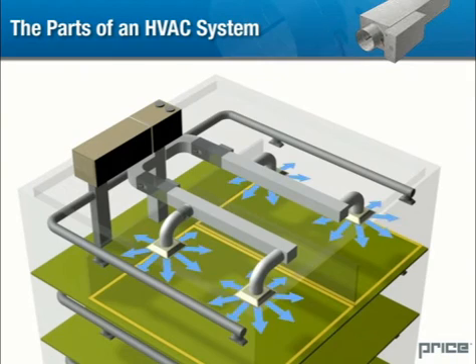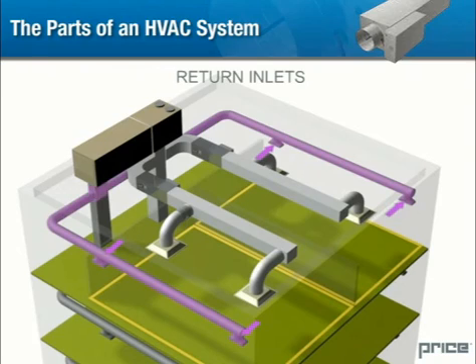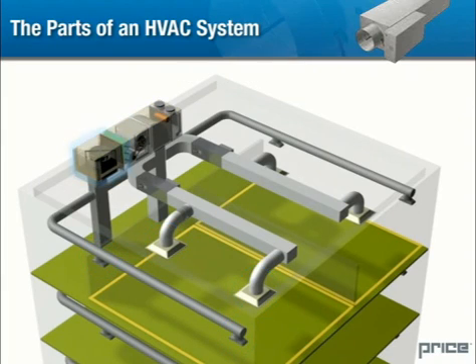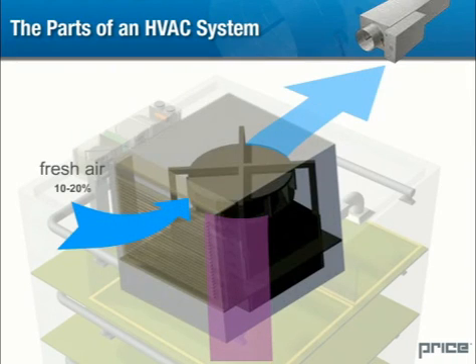Once air enters a space, where does it go? Air circulates through the return inlets and returns to the air handling unit. Unlike an air outlet, a return requires no sophisticated vanes. However, the relative location of the air inlets and outlets can be critical to the efficiency of the system. Upon returning to the air handler, a certain portion of the return air is exhausted and replaced with fresh exterior air — in an average office building or commercial space, approximately 10 to 20%.